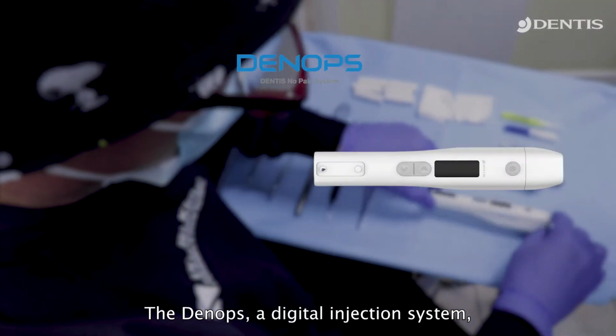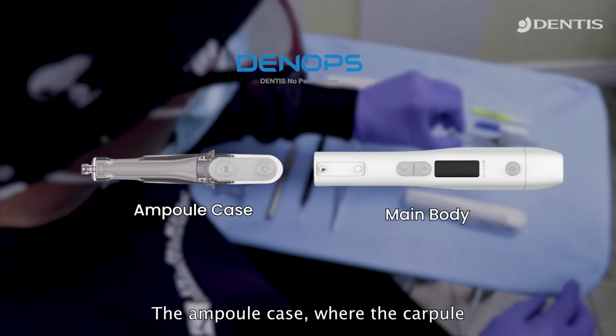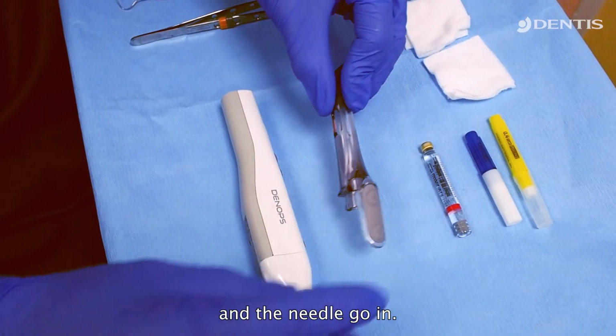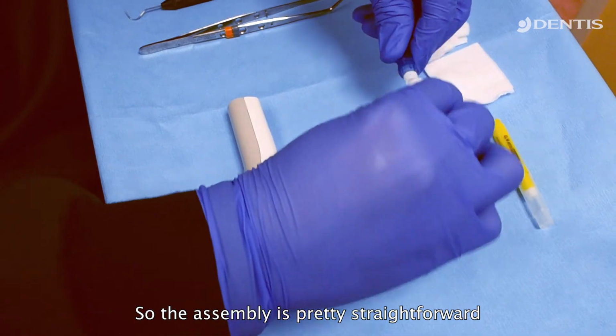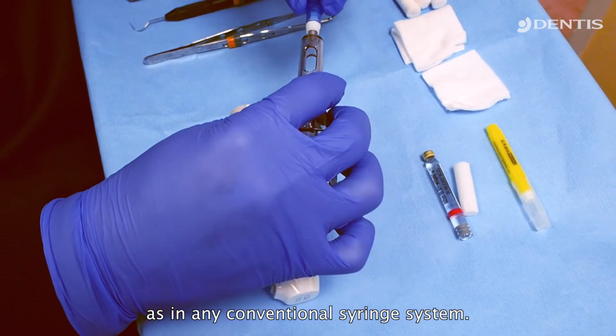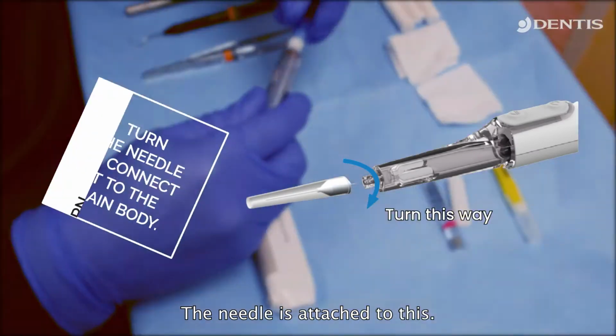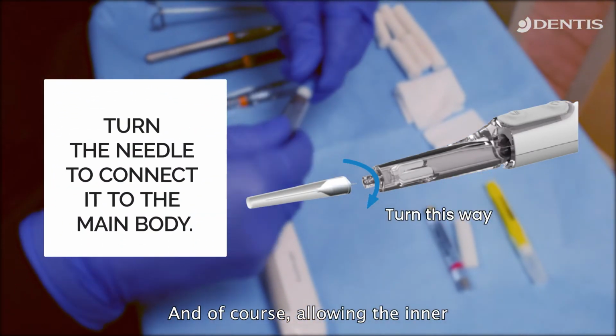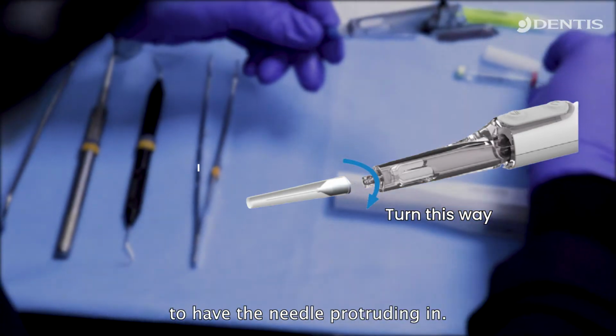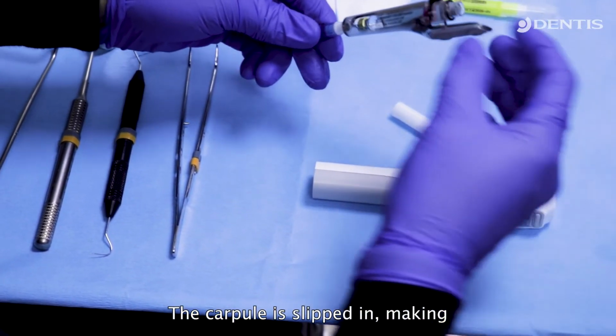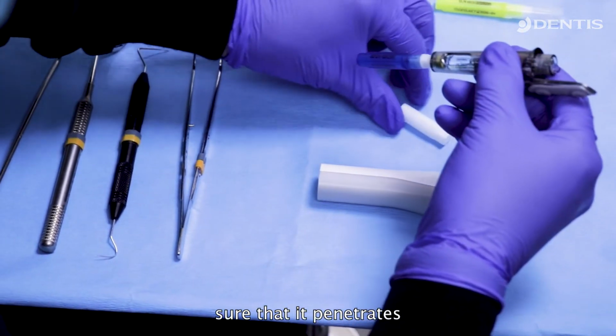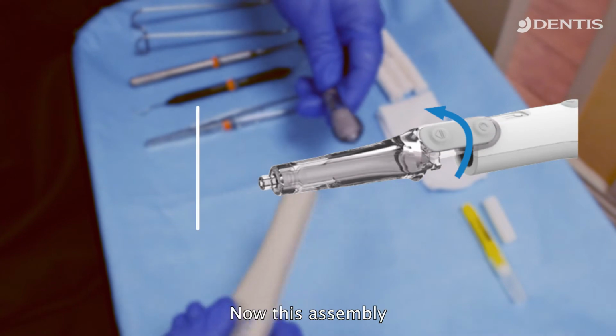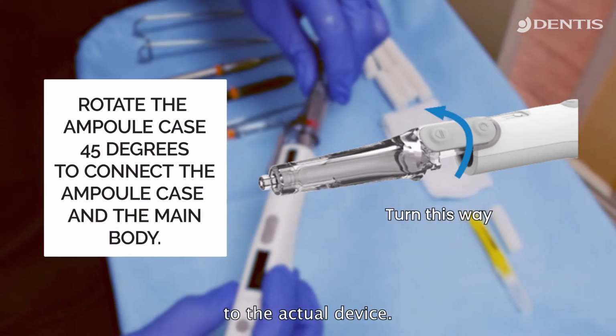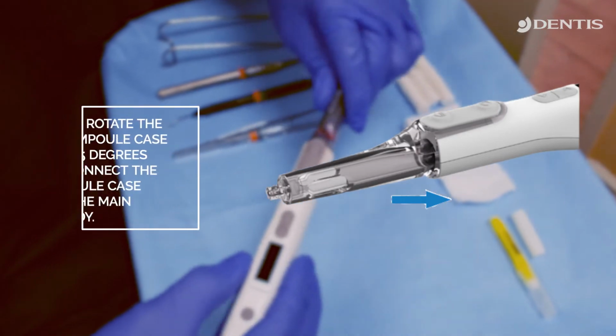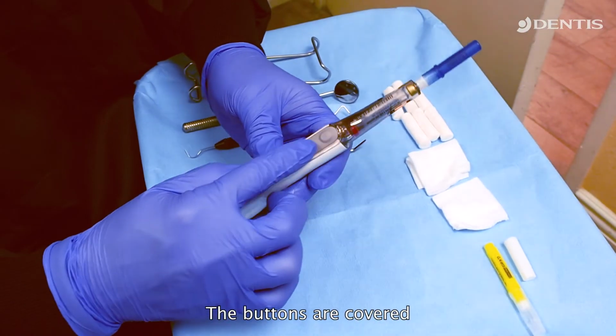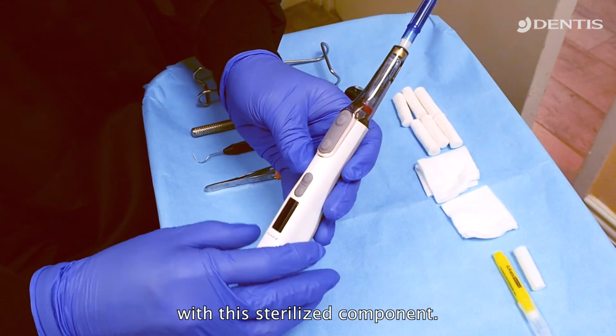The DENOPS digital injection system has the main device, the carpule holder, where the carpule and the needle goes in. So the assembly is pretty straightforward, as in any conventional syringe system. The needle is attached to this end, and of course allowing the inner part of this cylinder to have the needle protruding in. The carpule is slipped in, making sure that it penetrates into the actual needle. Now this assembly is to be brought together to the actual device. By twisting this in, it's secured, and the buttons are covered with this sterilized component.